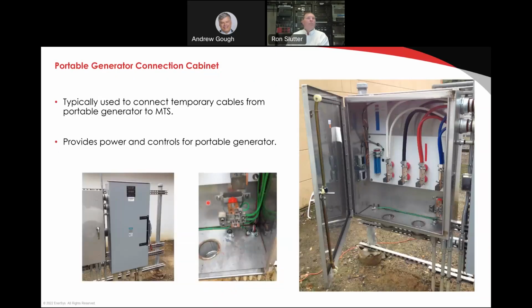All right, so moving on to the portable generator connection cabinet. You can see here on the right-hand side, that's the inside of the box. You can see that we have some nipples that pass through the bottom to allow the temporary conductors to be routed to the box and connected to the lugs. This is something that is made locally by someone. That is not a purchased box. That's something that is put together on site. They also do have boxes that you can buy. I'm going to show them to you in a minute.